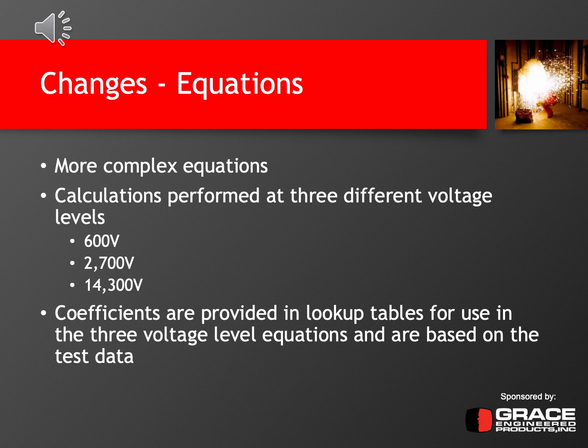So in summary, the equations have become much more complex than they were in the 2002 edition. For each of these equations, you need to perform calculations at 3 different voltage levels: 600 volts, 2.7 kV, and 14.3 kV, and then you interpolate to your actual system voltage, both in intermediate and in final. Coefficients provided in these longer equations are given in lookup tables for use in the 3 voltage level equations, and they are based on the actual test data. So they were empirically and statistically derived from the test data. Many commercial software programs already have these coefficients pre-programmed based on your voltage settings, so you may not have to look up the coefficients. But if you wanted to do hand calculations to verify the software calculations, this is how you would do it.